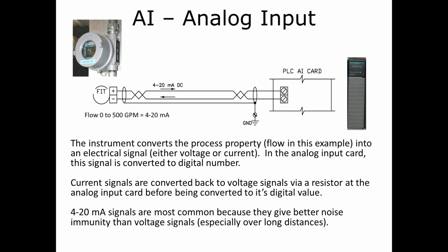But on this, for example, 4 to 20 is 16. Half of 16 is 8. So if you add 8 to the 4, that gives you 12. So if the flow indicating transmitter was sending a 12 milliamp signal to the PLC card, and you knew it was scaled 0 to 500, you knew that 12 milliamps is halfway between the 0 to 500. So you would know that the flow indication is somewhere around 250. If everything's calibrated right and dialed in, you should have 250 gallons a minute going through that flow meter because you're getting a 12 milliamp signal.